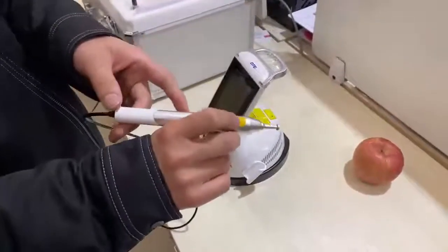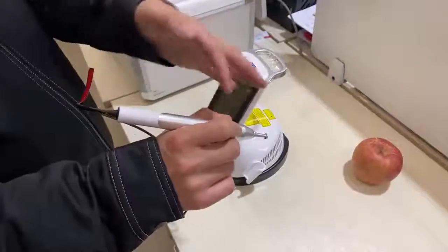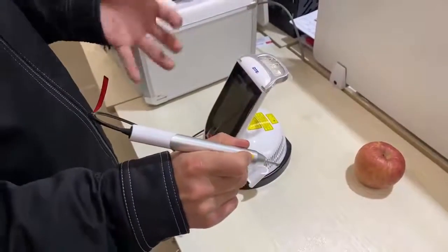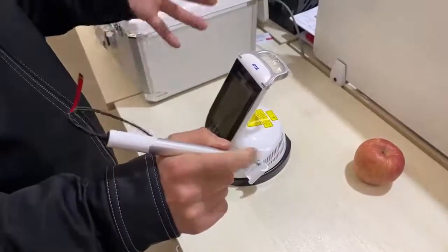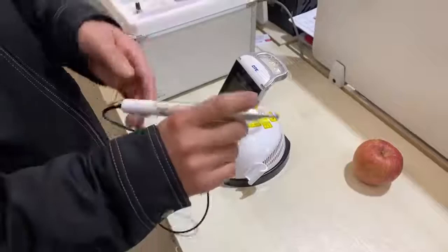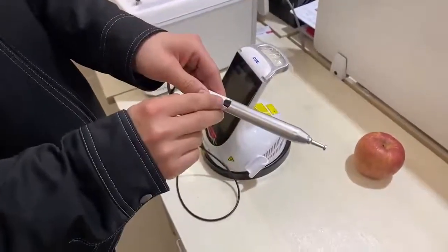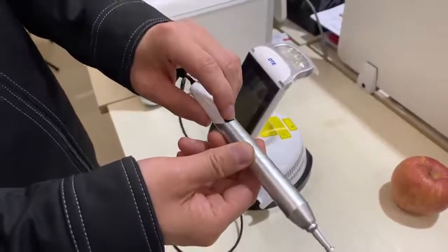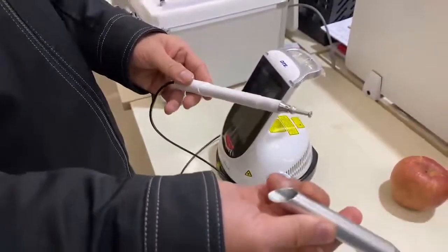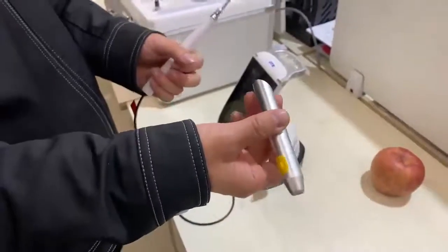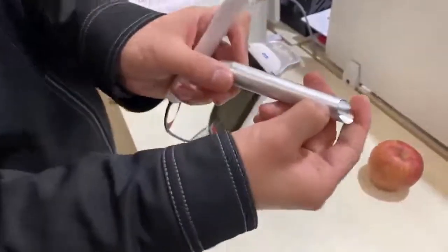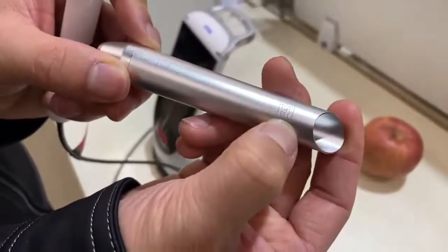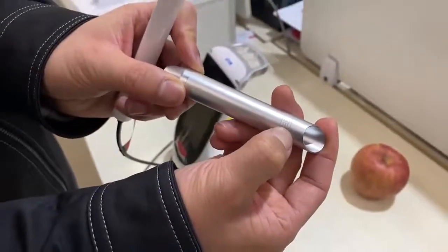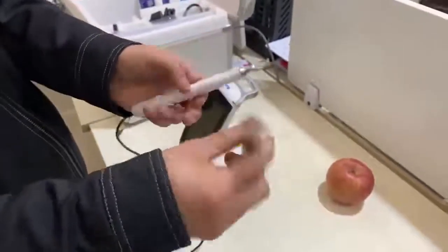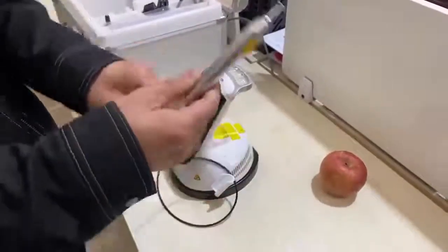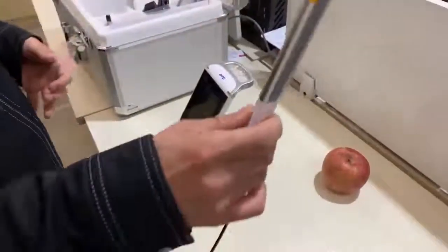And also we have a button here, and if you press the button, laser will come out from the handpiece. But you have to press all the time. If you release the button, it will stop emitting laser. Okay, and here we can see a black button. If you press the black button, you can remove the handpiece sleeve. This handpiece sleeve can be autoclaved, and we can see a mark here. This mark means the handpiece sleeve can be autoclaved under 134 degrees centigrade. Okay, so now we put on the handpiece sleeve. Okay, so this is about handpiece.